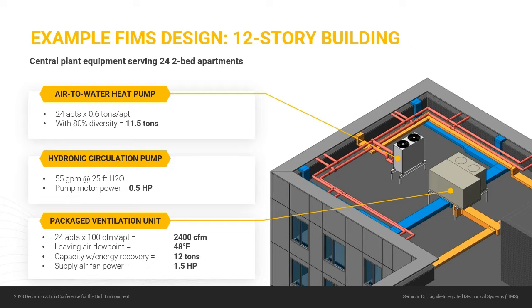And then looking at the package ventilation unit, again being conservative, assuming 100 CFM per apartment, and also assuming we're really cooling that air, really drying it down to a dew point of 48 degrees, which is pretty aggressive. Still, with energy recovery, that'll be a roughly 12-ton unit, and the supply fan power will be 1.5 horsepower.